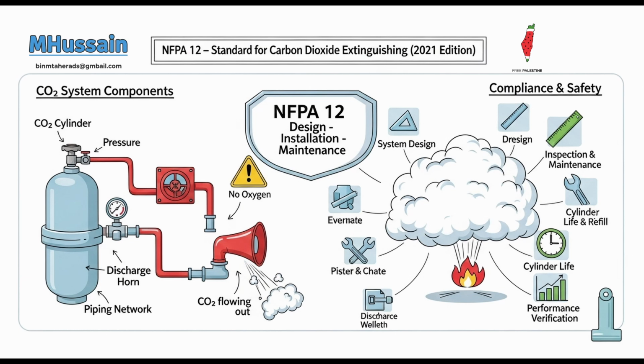This general prohibition is a cornerstone of the NFPA 12 standard, reflecting the extreme danger of CO2 in occupied areas. However, there are very specific, tightly controlled exceptions, each with a clear rationale. Okay, what are they? For example, total flooding systems are permitted when an inerting concentration is absolutely required and where alternative gaseous agents would either result in concentrations above their lowest observed adverse effect level, LOAEL. Okay, the point where it becomes harmful. Right, the lowest concentration at which adverse health effects are observed, or would reduce oxygen levels below a critical 8%, posing their own significant risks.